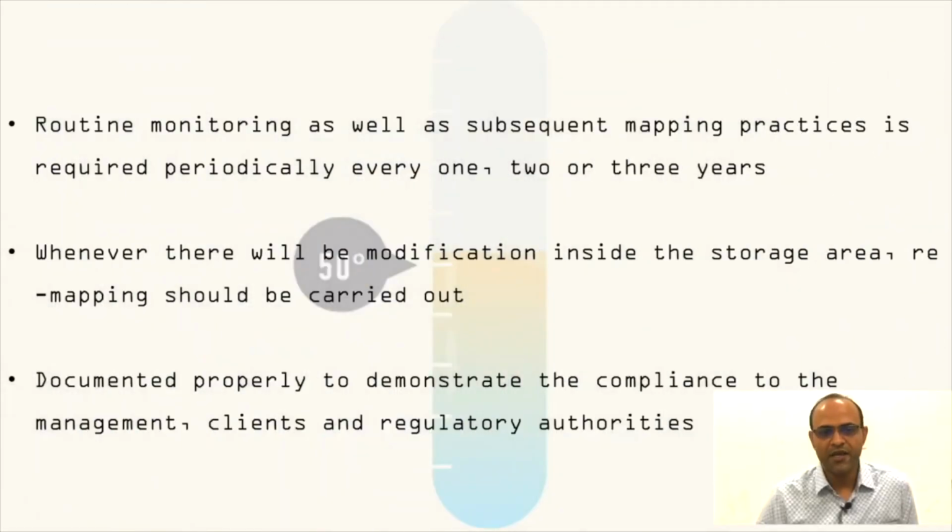Routine monitoring as well as subsequent mapping is required periodically, every 1, 2 or 3 years. Whenever there is a modification inside the storage area, remapping should be carried out. Everything should be documented properly to demonstrate compliance to the management, clients and the regulatory authorities.